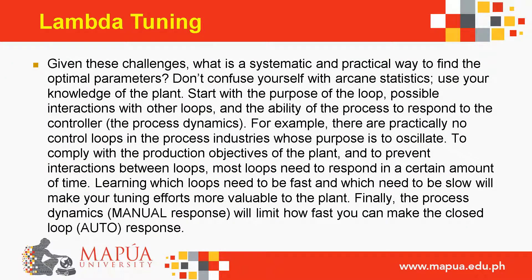Given these challenges, what is a systematic and practical way to find the optimal parameters? Use your knowledge of the plant: start with the purpose of the loop, possible interactions with other loops, and the ability of the process to respond to the controller. There are practically no control loops whose purpose is to oscillate. Most loops need to respond in a certain amount of time — knowing which loops need to be fast and which slow makes tuning more valuable. Process dynamics will ultimately limit how fast the closed loop response can be.